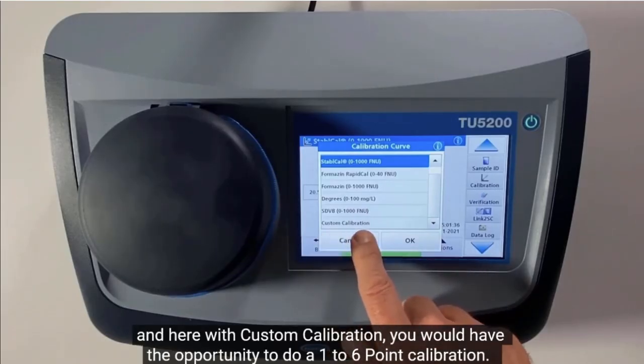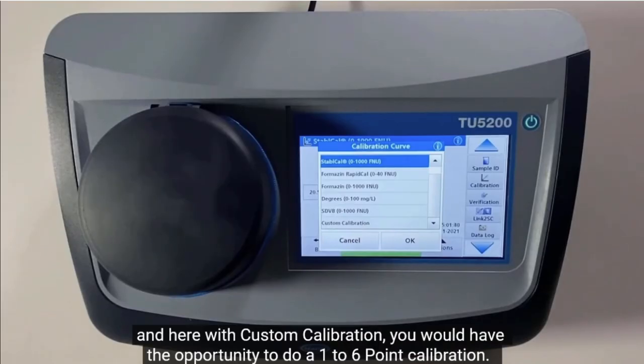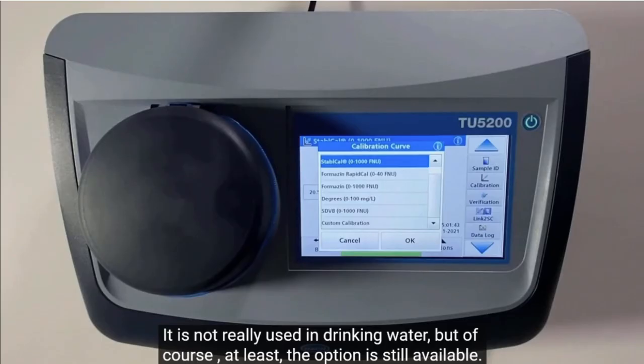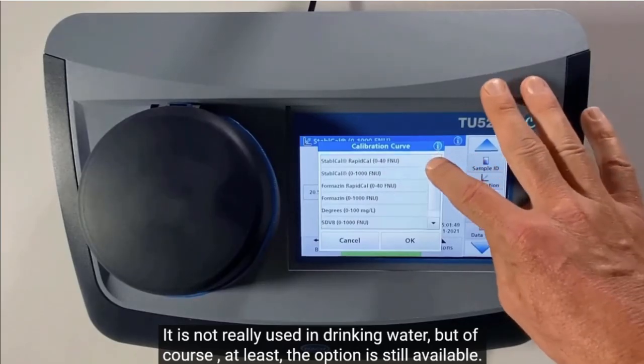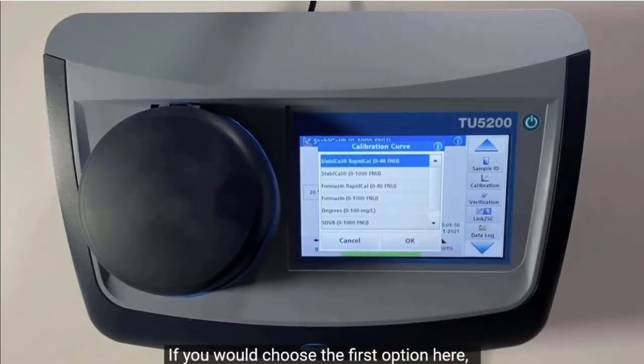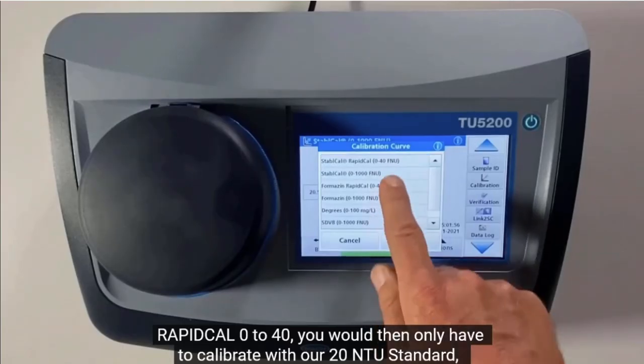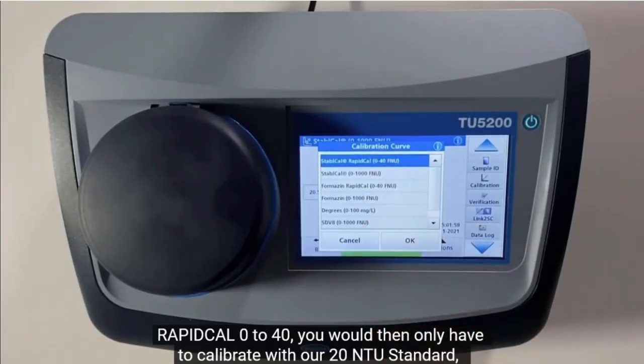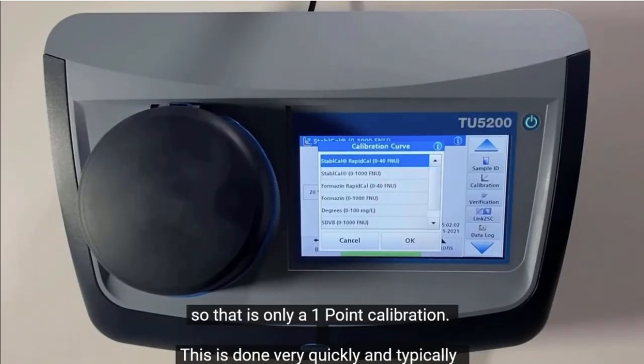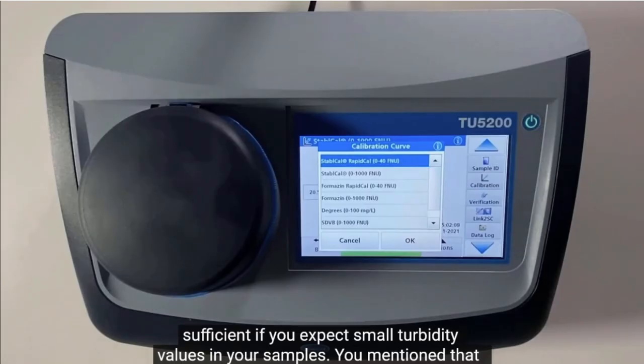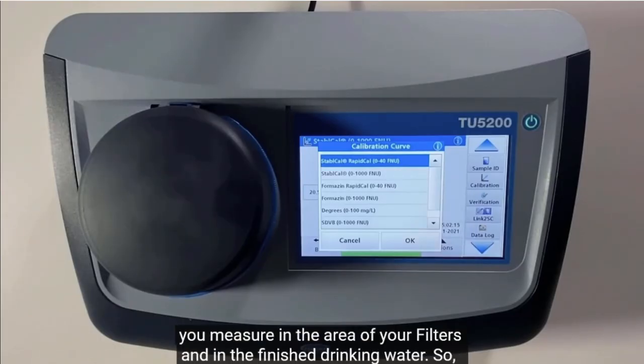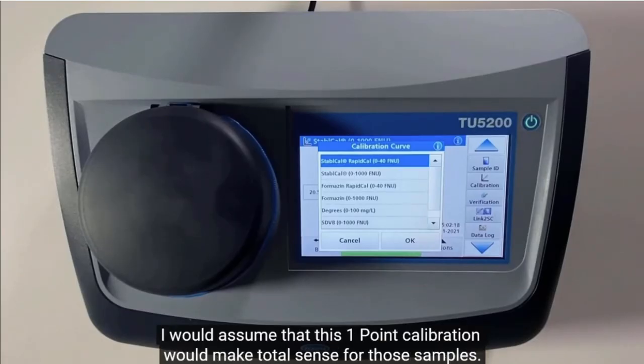And here with custom calibration, you have the opportunity to do 1 to 6 point calibration. It is not really used in drinking water, but of course, at least the option is still available. If you choose the first option here, Rapid Cal 0 to 40, you would then only have to calibrate with our 20 NTU standard. So that is only a 1 point calibration. This is done very quickly and is typically sufficient if you expect small turbidity values in your samples. You mentioned that you measure in the area of your filters and in the finished drinking water, so I would assume that this 1 point calibration would make total sense for those samples.